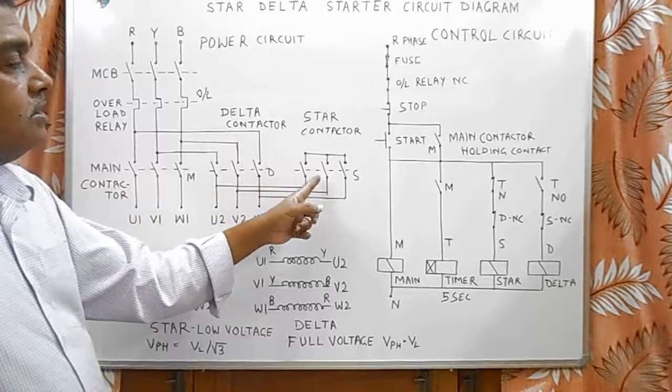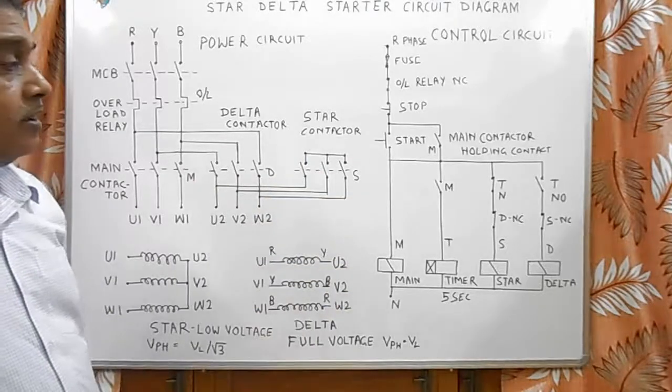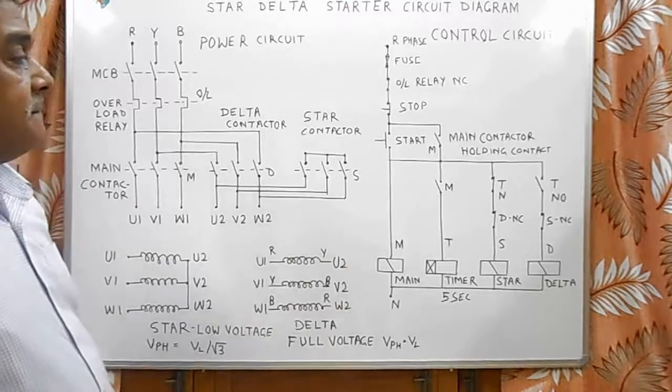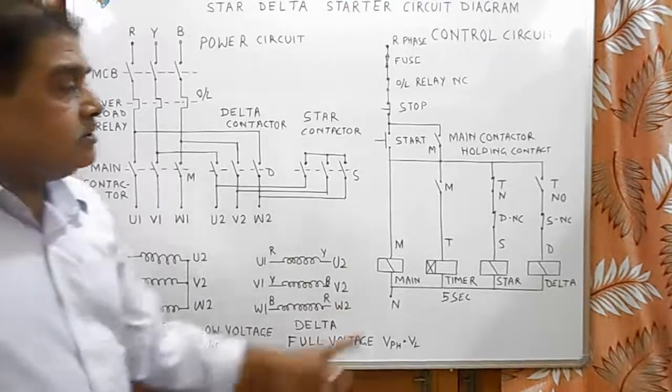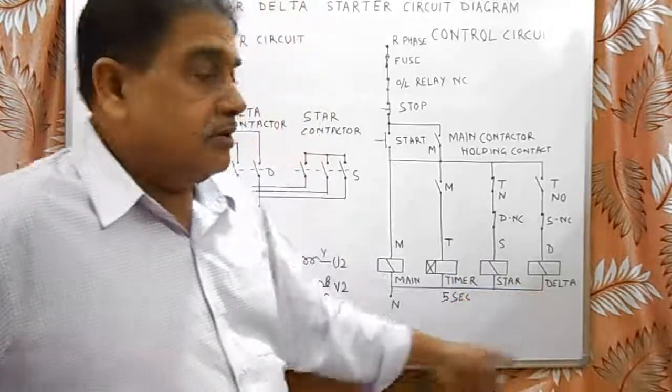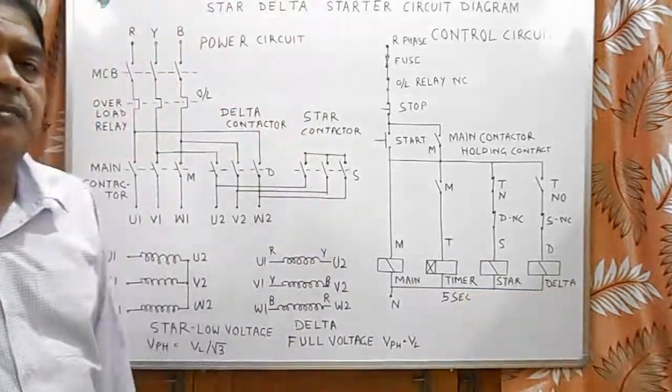Star contactor has already stopped, so short circuit is removed from this point. The delta NC contact and star NC contact are given here for making star and delta contactor interlocking, so that they cannot pick up simultaneously.